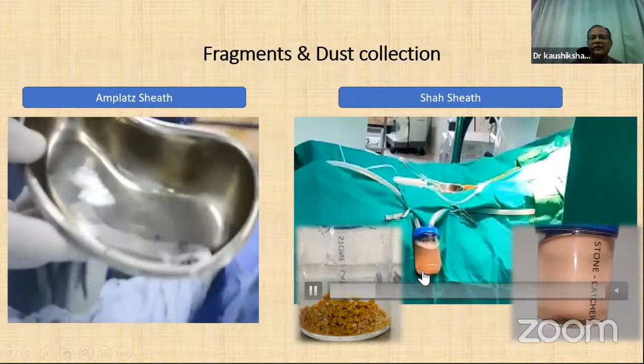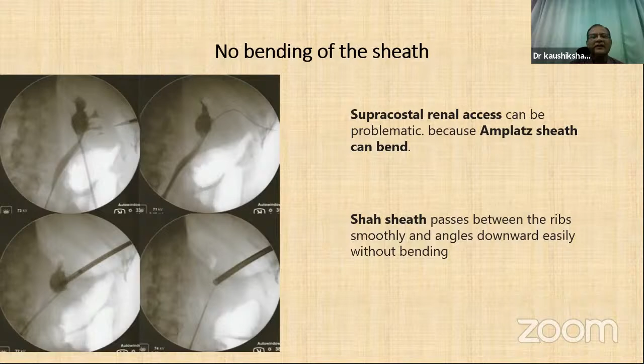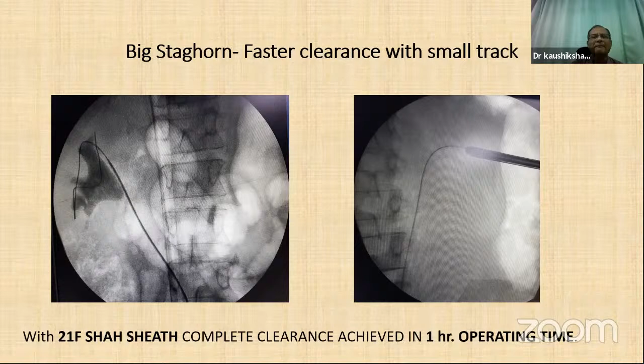There is no bending of the sheath because it is a metal sheath. Even if you go through the intercostal space, there is no buckling, and if you move, that doesn't break the nephroscope, and it is very easy to take out the fragments. And you can do a staghorn stone with a faster clearance with a smaller track. Here, with a 21 French sheath, the whole procedure was completed within an hour. That is a big advantage for staghorn stones also.